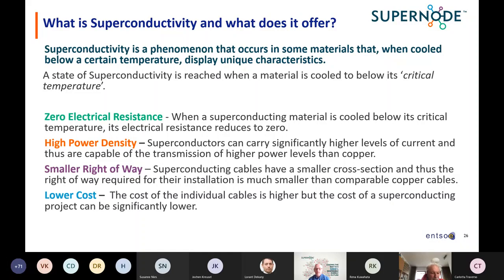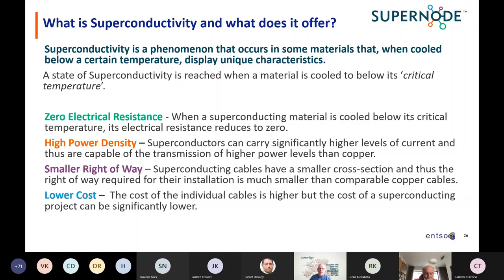High power density is a particular application — you can get more power into a smaller space, leaving you with a smaller right-of-way. For traditional cables handling large bulk power transfer you might need a 10-meter right-of-way, whereas a superconducting cable can reduce that to as little as a meter. The cable cost can be higher, but overall project cost can be lower, and we have seen commercial superconducting projects start to take off.